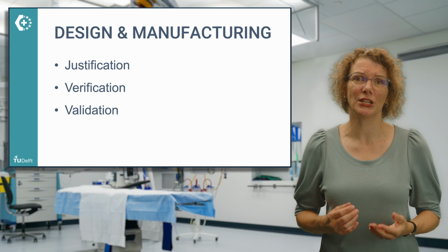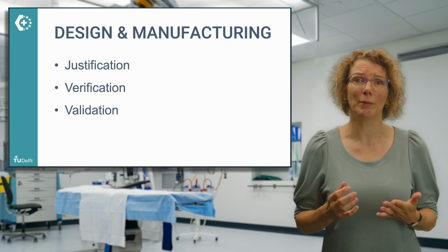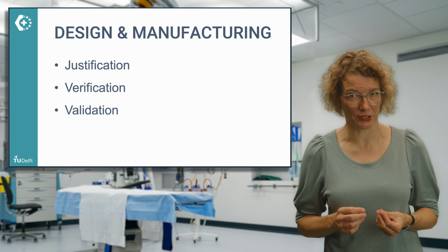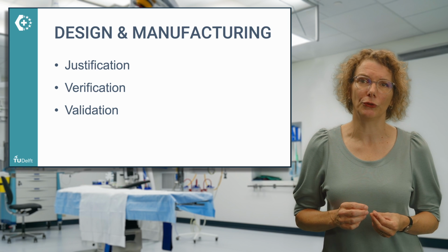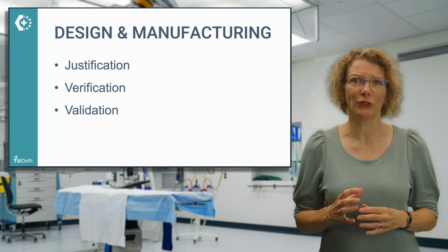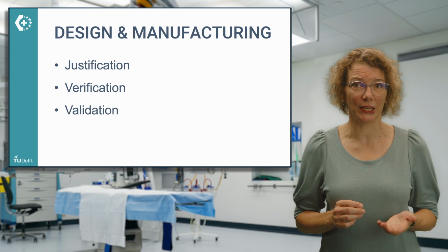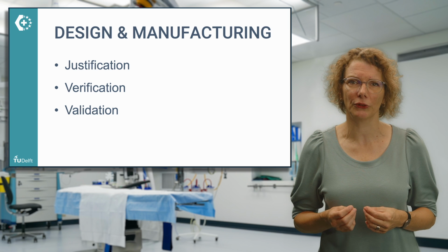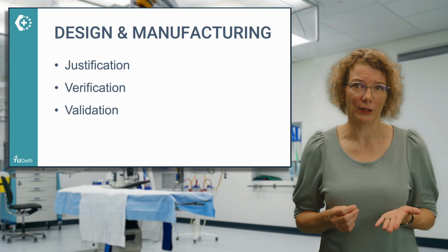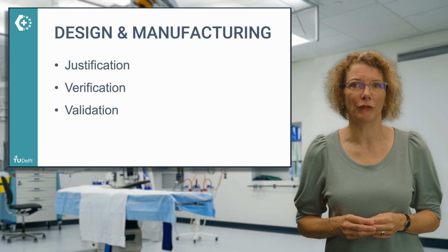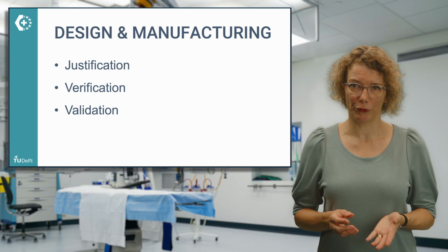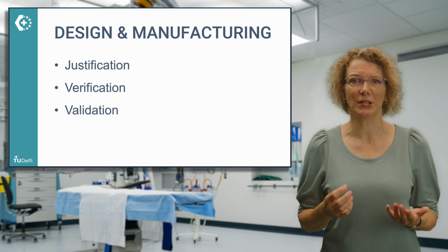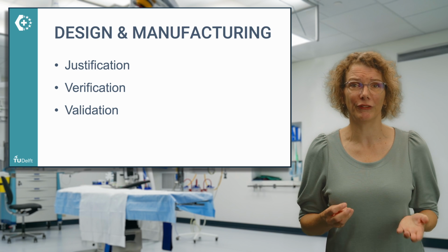The technical documentation should provide insight in the methods used, including study protocols for verification and validation tests, and the results and conclusions of these tests. This includes preclinical as well as clinical data on, amongst others, the device's physical characteristics, electrical safety, biocompatibility, and stability, including shelf life. Overall performance and safety of the device should also be well documented and demonstrate that the risks are adequately mitigated by the device design.